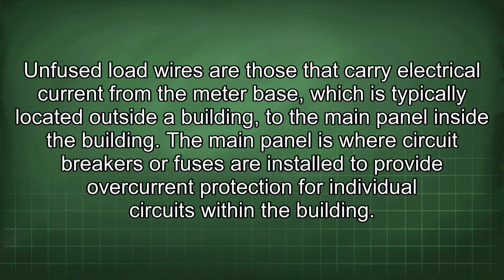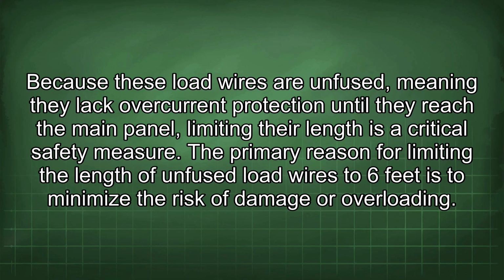Unfused load wires are those that carry electrical current from the meter base, which is typically located outside a building, to the main panel inside the building. The main panel is where circuit breakers or fuses are installed to provide overcurrent protection for individual circuits within the building. Because these load wires are unfused, meaning they lack overcurrent protection until they reach the main panel, limiting their length is a critical safety measure.